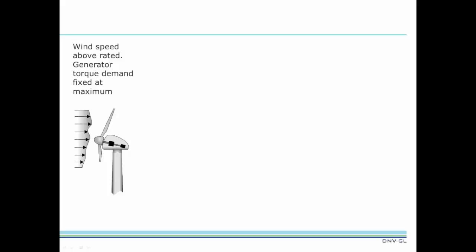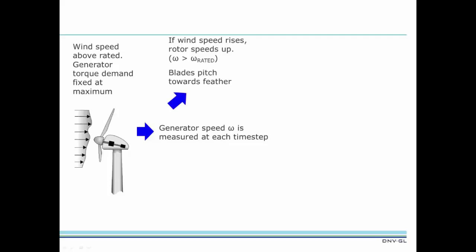Let's look at a summary of that. With wind speed above rated, the generator torque demand is fixed at the maximum value. Generator speed is measured at each time step. If wind speed rises, the increased aerodynamic torque will cause the rotor speed and output power to increase. The response to this increase in speed is to pitch the blades towards feather. This reduces the aerodynamic torque, slowing the rotor. The rotor returns to rated rotor speed, and power remains constant.